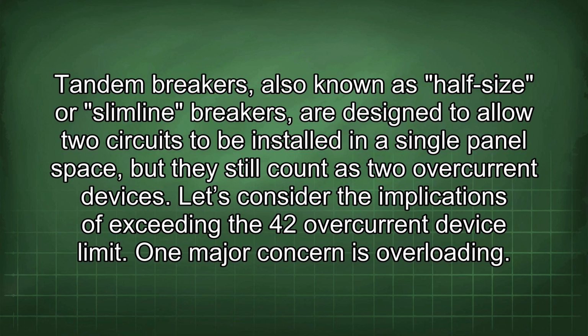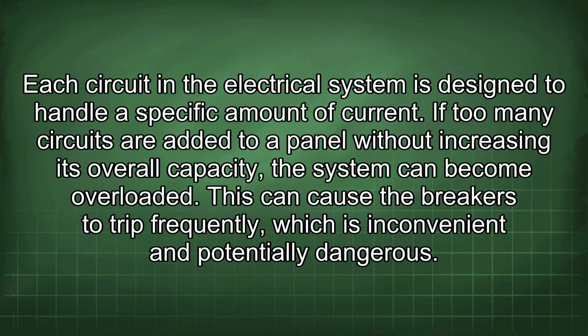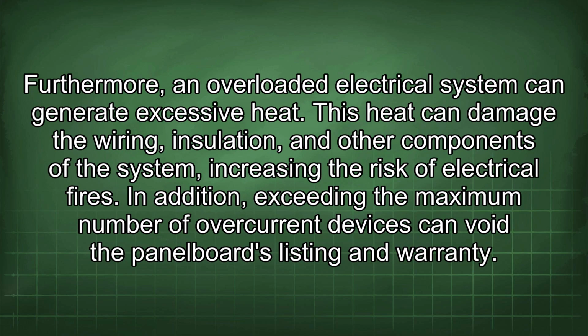Let's consider the implications of exceeding the 42 overcurrent device limit. One major concern is overloading. Each circuit in the electrical system is designed to handle a specific amount of current. If too many circuits are added to a panel without increasing its overall capacity, the system can become overloaded. This can cause the breakers to trip frequently, which is inconvenient and potentially dangerous. Furthermore, an overloaded electrical system can generate excessive heat. This heat can damage the wiring, insulation, and other components of the system, increasing the risk of electrical fires.